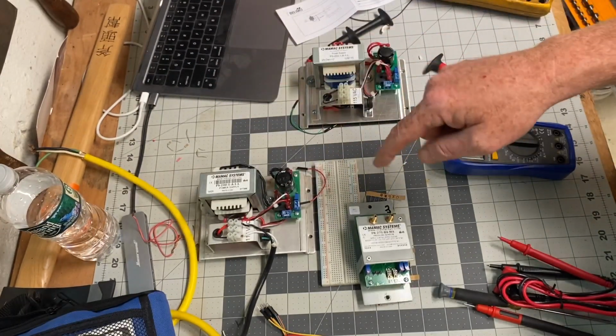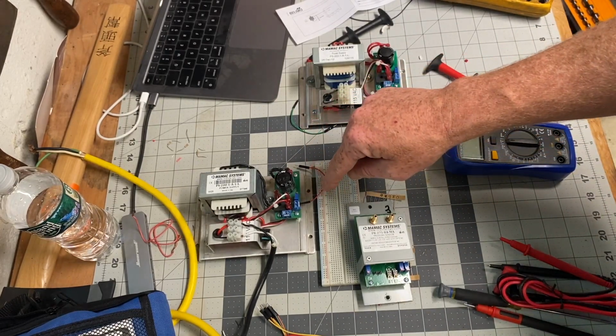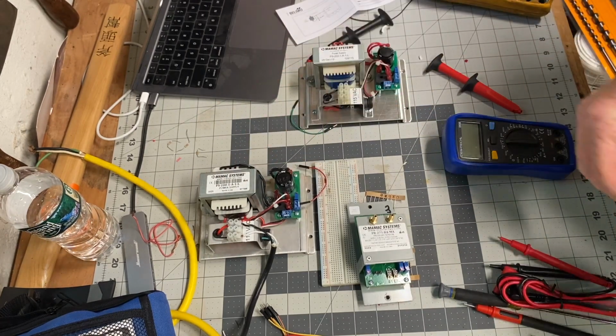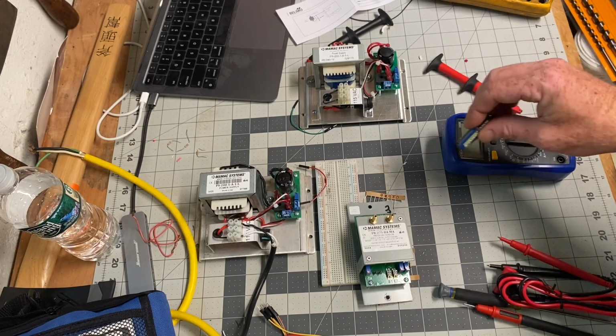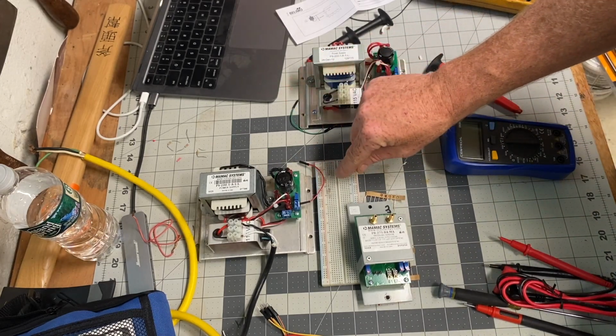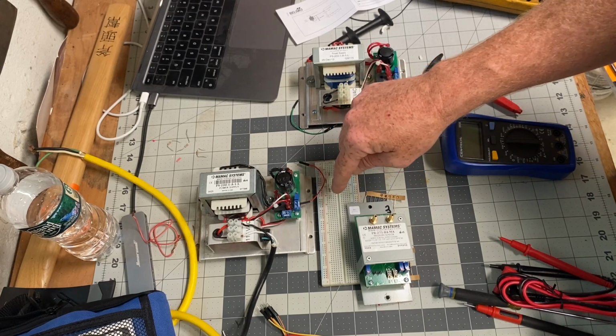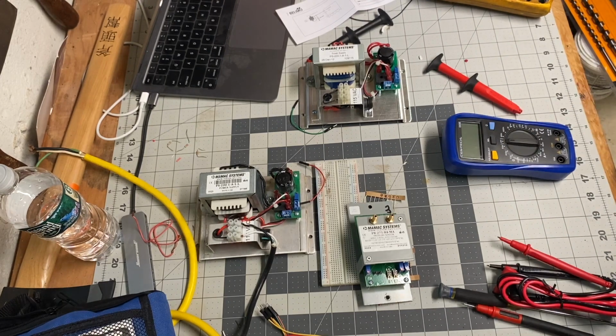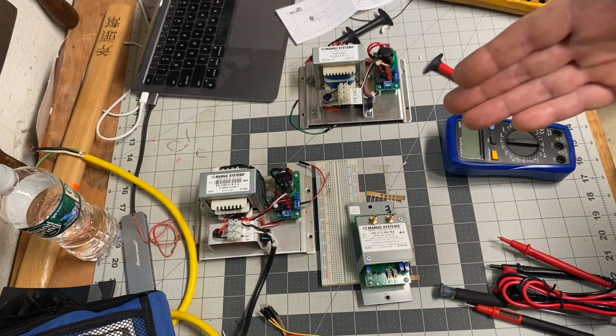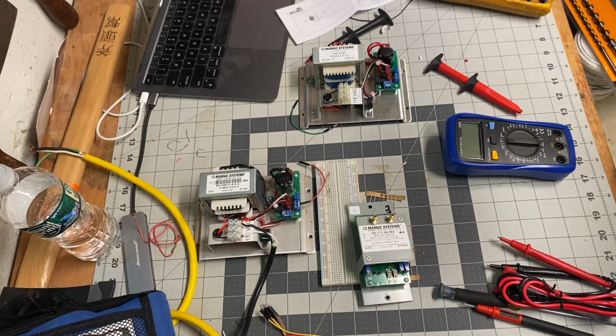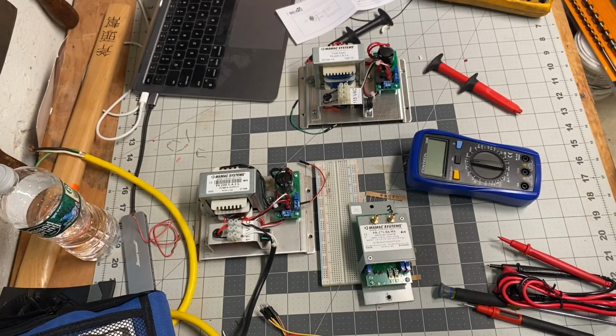I want to pull into the building automation system the milliamp reading for the voltage output, right? So if it's outputting 24 volts DC and I put it through a 2000 ohm resistor, that should give me 12 milliamps, and I can feed that 12 milliamps back into the BMS panel, and I can put it into a table statement where at 12 milliamps it reads 24 volts DC. So the lower the voltage goes, the lower that milliamp reading, and then alarm it and be able to proactively catch a bad transformer. Right. So let me get this meter fired up, and we'll give it a test.